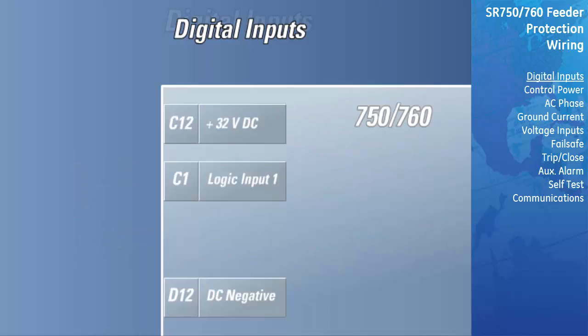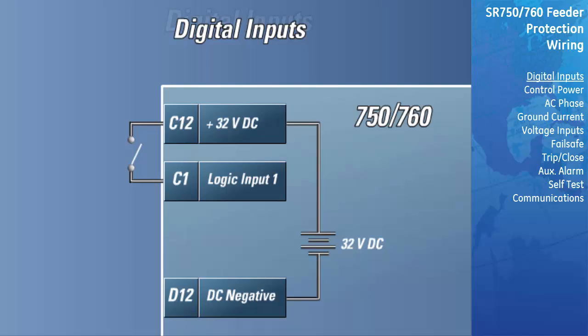When wiring the digital inputs to the relay, it is important that terminal C12 is used as the common for all dry contact connections. This terminal is connected to an internal 32-volt supply, which is used to power the digital input circuitry. Connecting an external source of power or using a wet contact connection with this terminal will damage the relay. When using a wet contact connection, use terminal D12 as the common. The negative side of the external supply must be connected to this terminal. Improper orientation of the wiring can result in damage to the relay.